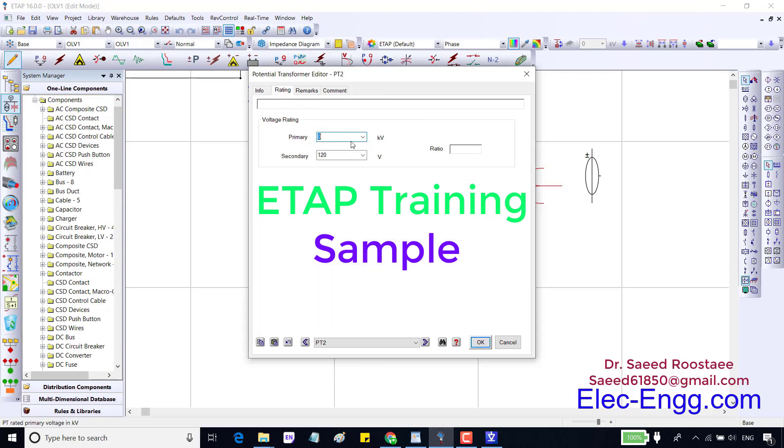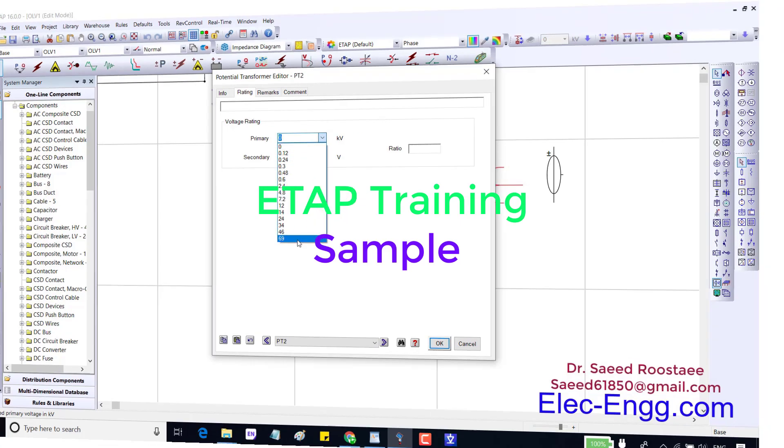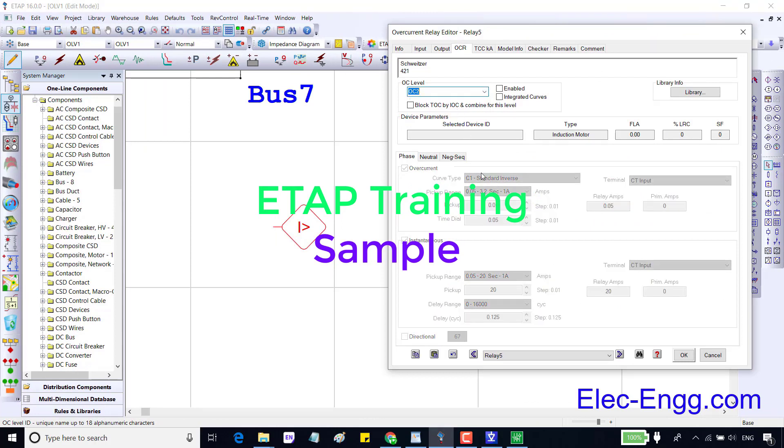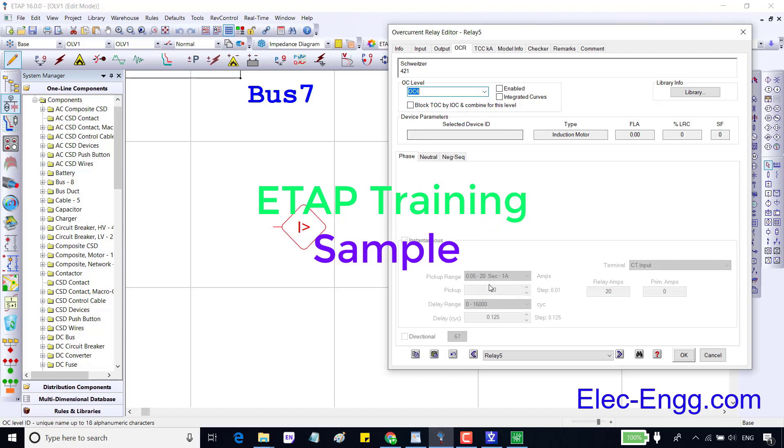In the rating page we can specify the PT rating. Here we should select the standard value from the drop down. This relay has four levels in ETAP and if we check the stages of the relay in the relay configuration software SEL relay configuration software, it should be the same in ETAP. This relay has three IDMT and four DMT stages.